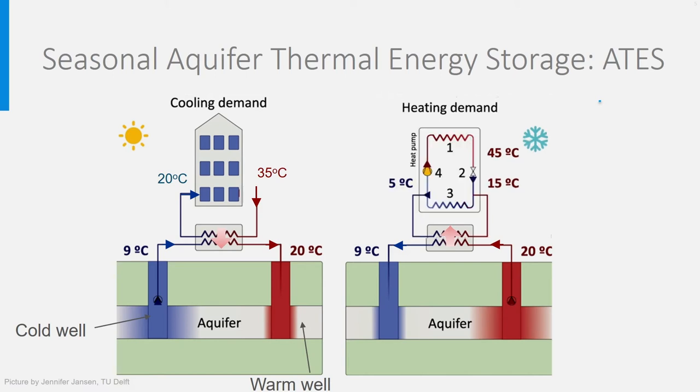Because the heat source has now a very high temperature, the COP will be high too. Typical COPs for these systems in the Netherlands are around 6 to 8 and the EER also.